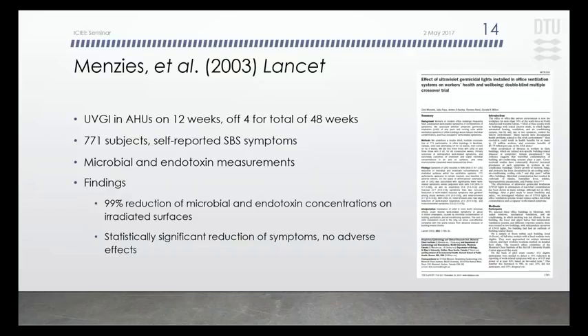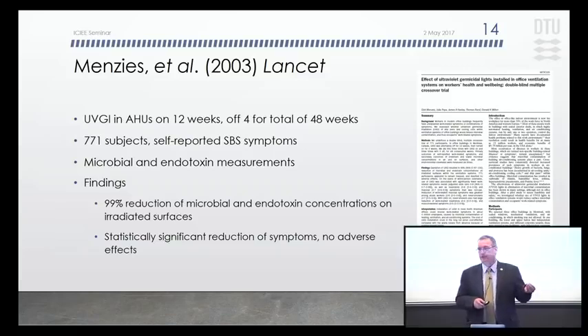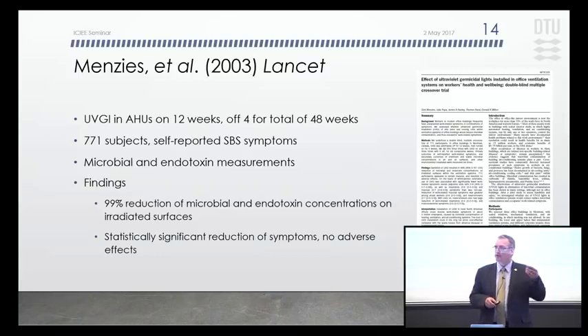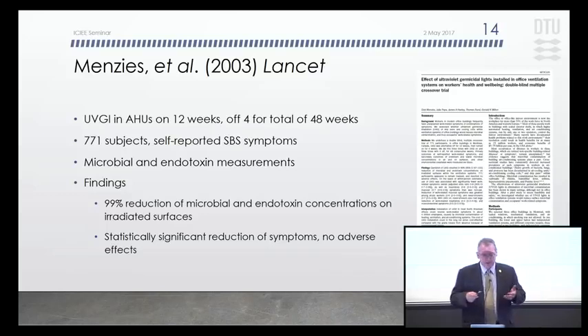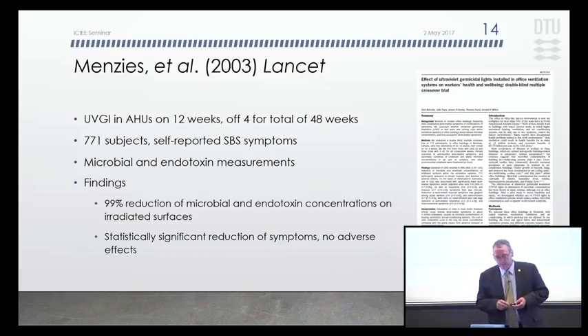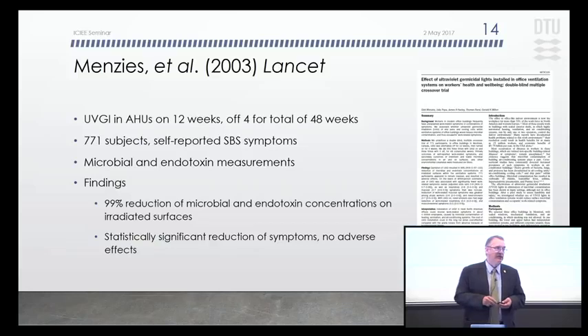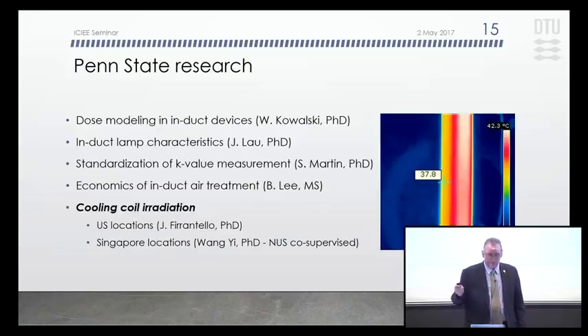A much more recent study was done by Menzies, Canadian, and published in The Lancet. This was looking at sick building syndrome symptom incidence in 2 office buildings where UVGI was installed in the air handling units, and the study was run double-blind. So neither the researchers nor the occupants knew when UVGI was operating. They surveyed for sick building syndrome symptoms during both periods and also did measurements in those buildings of the surface and air microbial and endotoxin concentrations, and found large reduction in concentrations on surfaces and air, and concluded there was a statistically significant reduction in the SBS symptoms. This was, again, a very persuasive study, but there haven't been enough yet. That's true of many topics in our field.